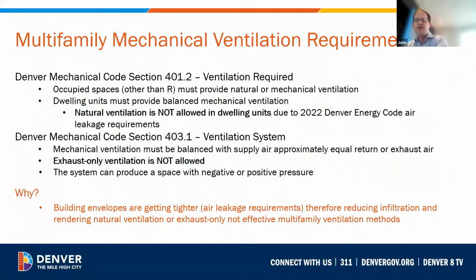The Denver Mechanical Code does not allow for exhaust-only ventilation as a mechanical ventilation strategy in any building type. Where mechanical ventilation is provided or required, ventilation must be provided by a combination of supply and return or supply and exhaust. So a balanced system is required.